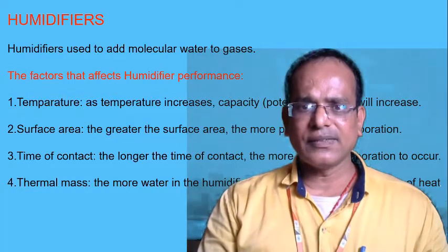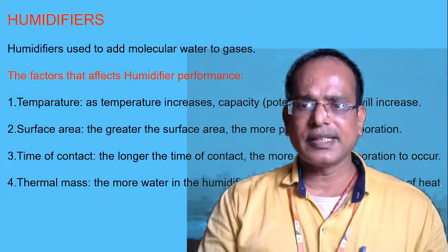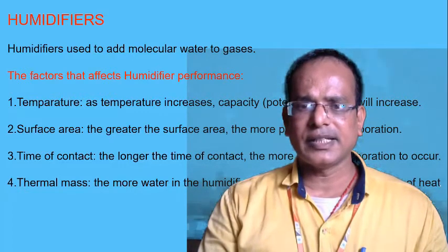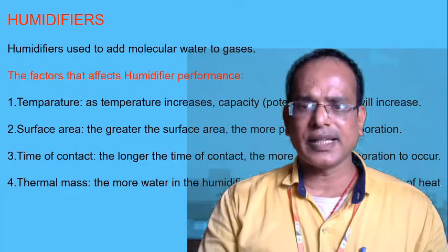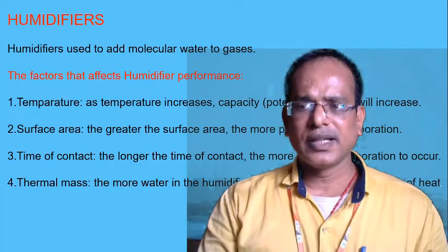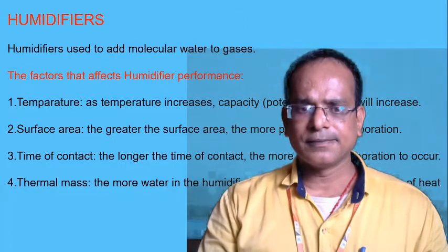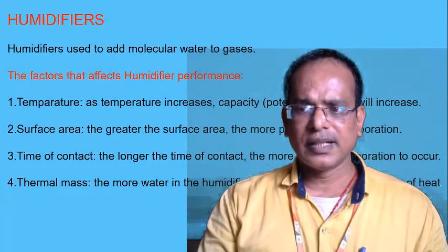The factors that affect humidifier performance: one is temperature. As the temperature increases, the capacity, that is the potential humidity, will increase. Second one, surface area. The greater the surface area, the more potential for evaporation. Third, time of contact. The longer the time of contact, the more time for evaporation to occur. Fourth one, thermal mass. The more water in the humidifier, the more potential for transfer of heat.